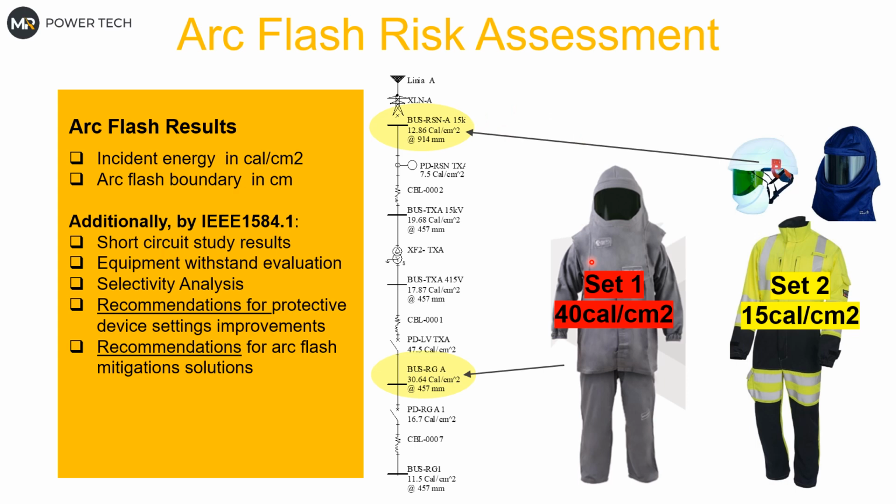And there is one hidden thing behind it, because you may see that on the low voltage we actually have higher energy than on the medium voltage. And that's very common. That's because low voltage is actually more dangerous in this case. It's not logical, but that's because of how we design the systems.